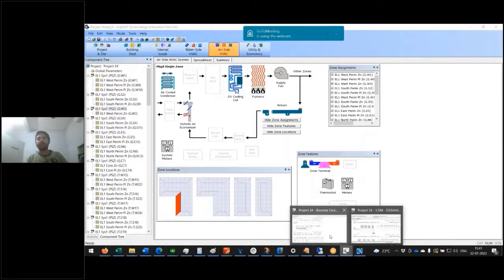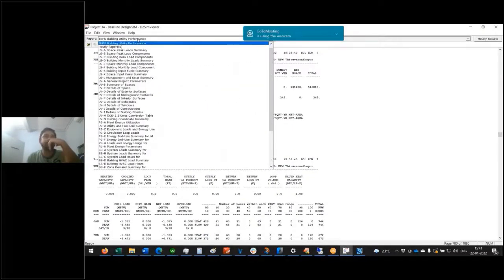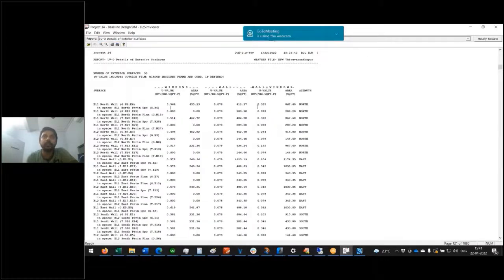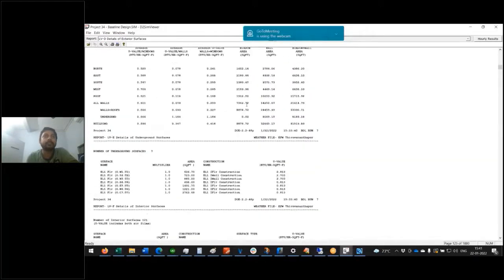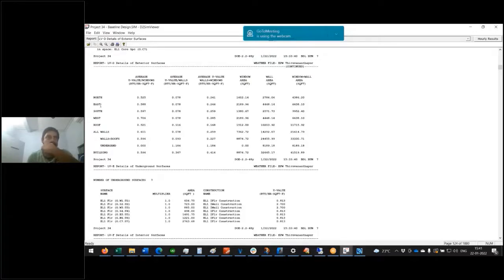Okay, let's understand a bit more about the reports also. How can you find window to wall ratio? That comes under details of exterior surfaces. Keep scrolling down until you find a page something like this, where it gives each orientation and roof, the average U values, the window area, the wall area, and window plus wall area. So for each orientation, you can get these values. Window area divided by window plus wall area will give you the window to wall ratio of that orientation. And if you want it for the whole building, take all walls. Don't take walls plus roof.